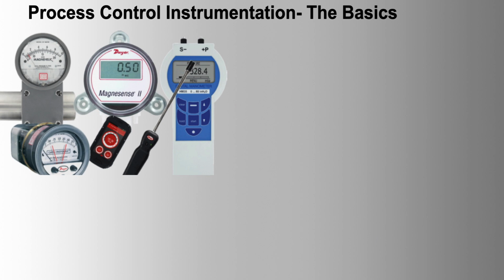Level instruments. 1. Measurement range and accuracy. Ensure level instruments can measure the full range of levels expected with the required accuracy. 2. Process conditions. Consider temperature, pressure, and chemical properties of the process fluid when selecting level instruments. 3. Measurement technology. Choose the appropriate technology, e.g. radar, ultrasonic, float, based on process conditions and tank geometry.